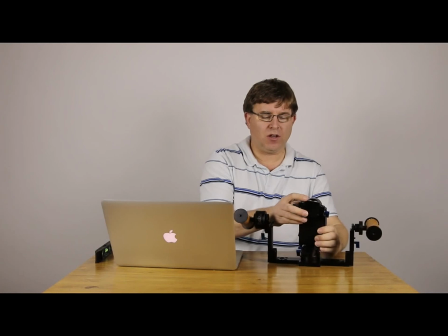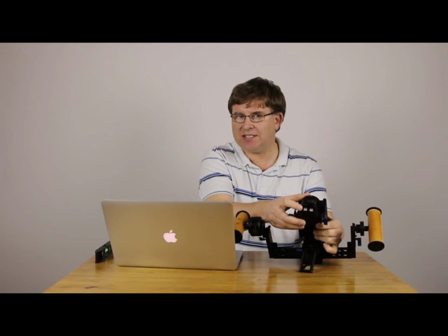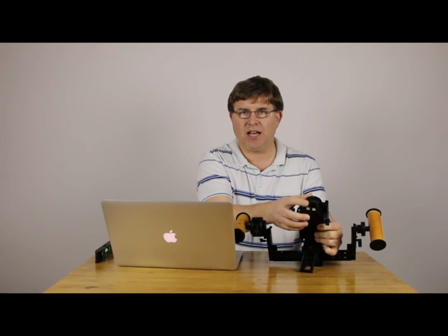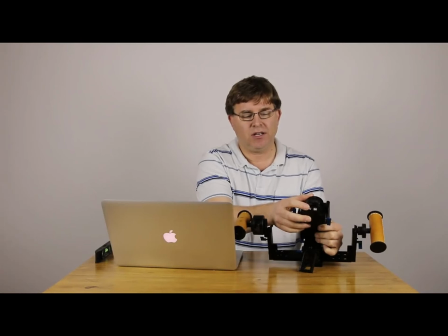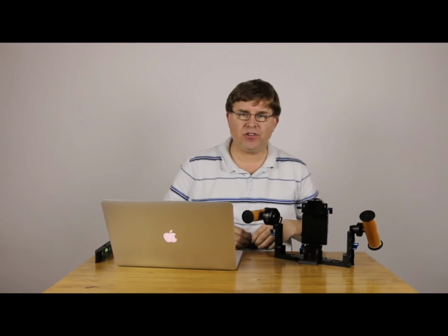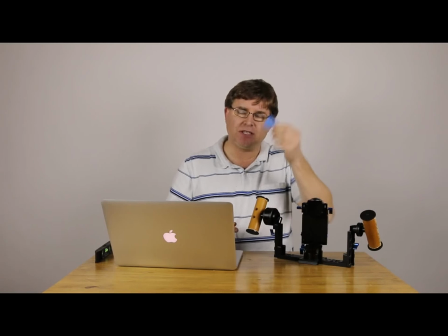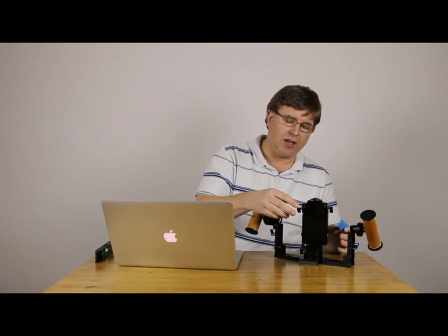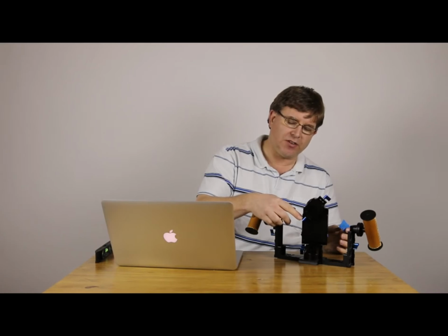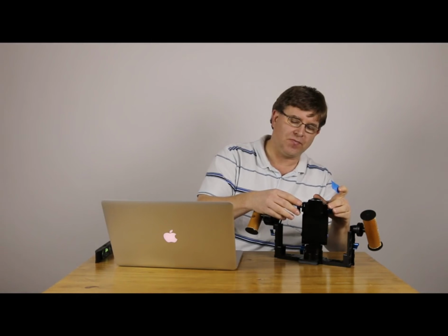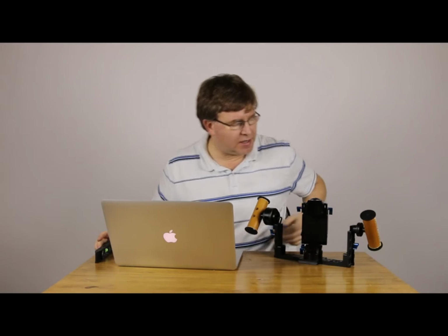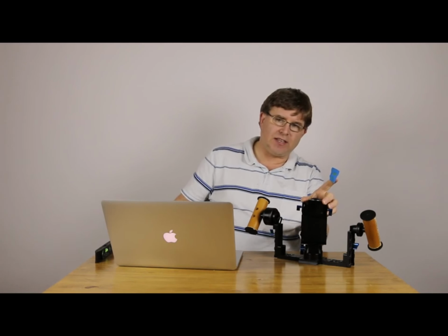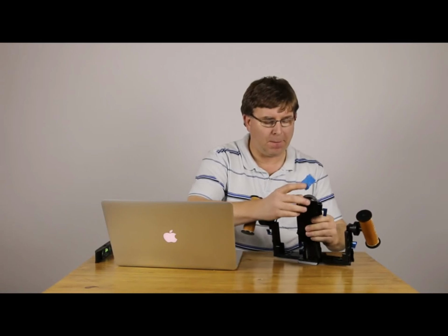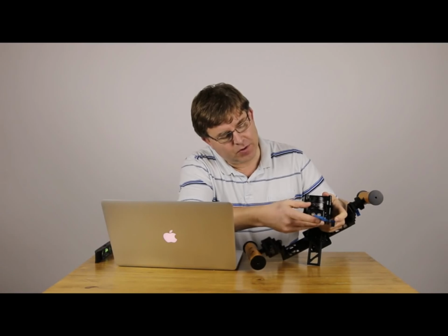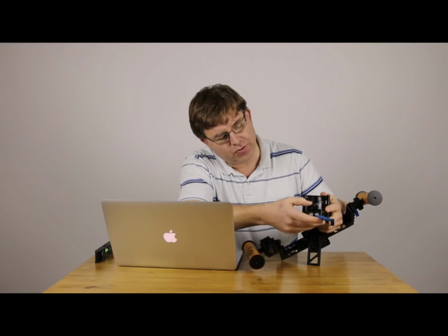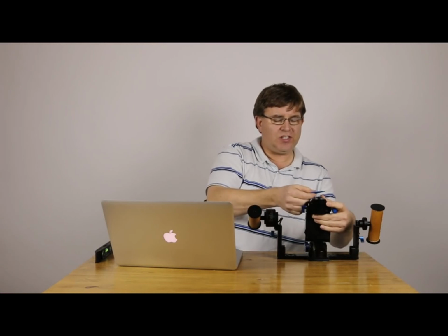So the first one, of course, is always with the LEMO port straight up. Now if you have a standard helix, you might have an SDI port coming out the top of this, and you need to make sure that the SDI port is up. Okay. And a little bit of a practical tip here. Here in the shop, one of the things that we'll do is we'll actually use a piece of tape. Some of you might have noticed that when we move this, it has a tendency to move in little steps because there are, of course, magnets inside these electric motors. And so we might get it exactly level where we want it, and then it doesn't quite stay. And so we'll often go ahead and put a piece of tape right here between this crack, the moving part of the motor and the part that does not move, the rotor and stator, and we'll actually tape it into position.